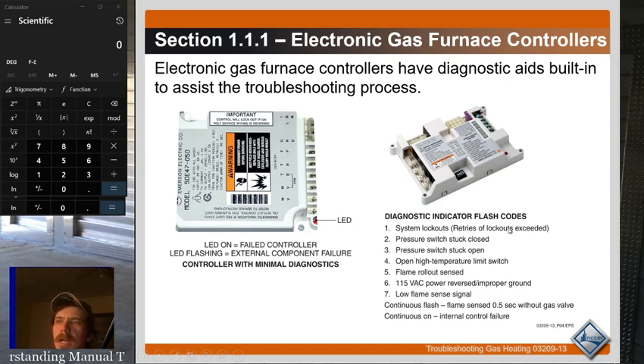You have system lockouts, so it locked out because it tried to light too many times and it didn't work. The pressure switch is stuck closed. The pressure switch is stuck open. A high limit switch or a flame rollout. A 115 volt power reversed or an improper ground, and a low flame sense signal. The most interesting one here is the power reversed.